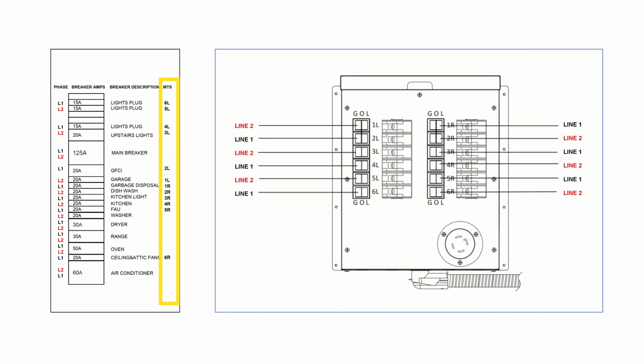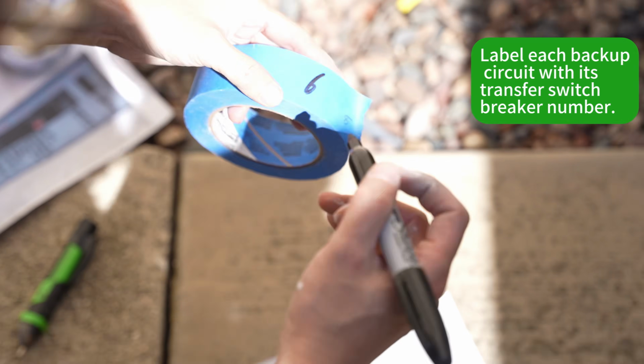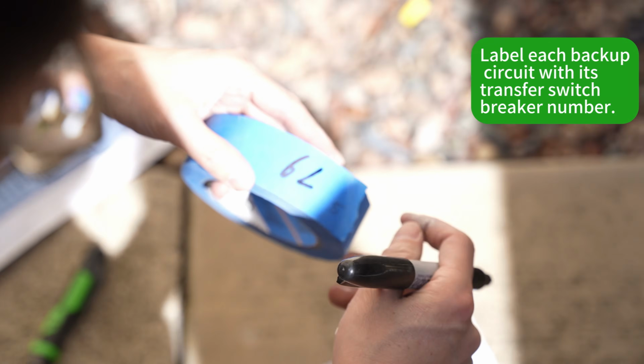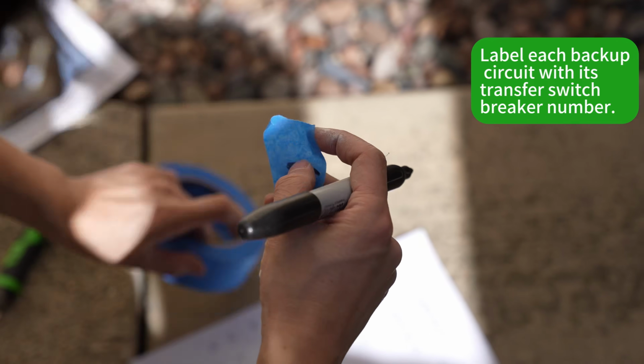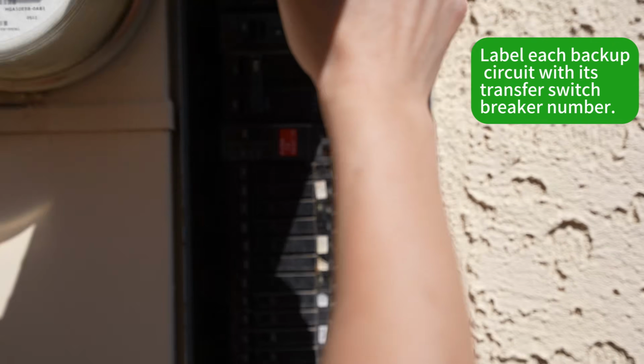Assign a transfer switch breaker number to each selected backup circuit on the panel schedule. Make sure the backup loads are properly balanced between L1 and L2. Label each backup circuit with its corresponding transfer switch breaker number.